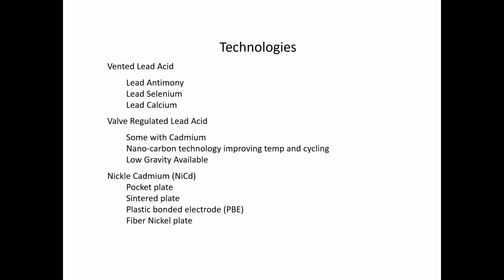There are some new technologies being used in the negatives, the nanocarbon technology now in valve regulated batteries, improving their ability to operate in hot, high temperature environments, and also improving cycling capability. And there is a low gravity version available. The reason the low gravity valve regulated battery was developed was so that it could be installed in parallel with vented lead acid batteries. Vented lead acid batteries typically float around 2.21, 2.22 volts per cell. Standard valve regulated batteries float around 2.25. So they made a low gravity version to float around 2.21, so they could be paralleled with lead acid.